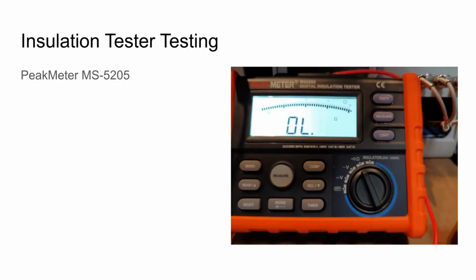The relay is rated by the manufacturer to hot switch up to 250 volts AC and up to 30 volts of DC and withstand a kilovolt of AC across open contacts. I decided to risk connecting a relay to my insulation tester to measure leakage resistance across the normally open contacts. My insulation tester is a Peakmeter MS5205 digital insulation tester. It takes three hands to take a picture, hold the probes, and hold down the safety measurement button. So, this is merely a picture of the resistance of the normally open contacts on relay J2.